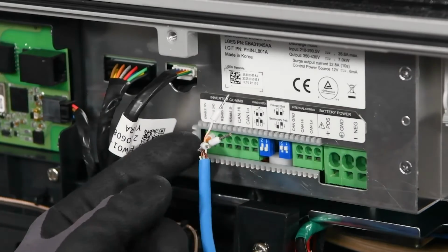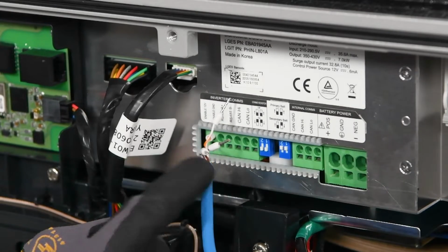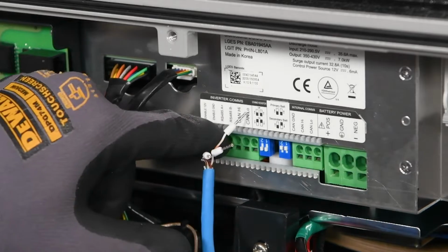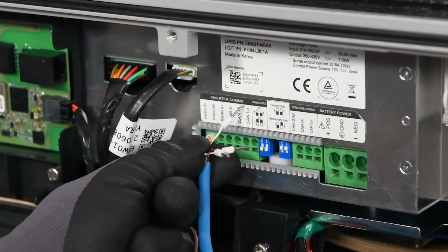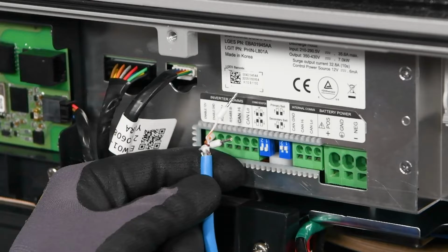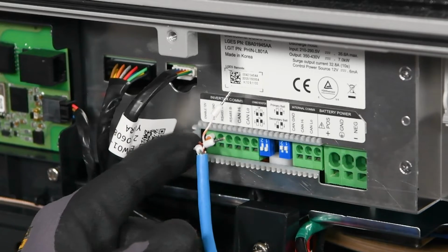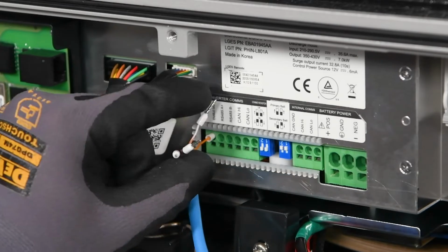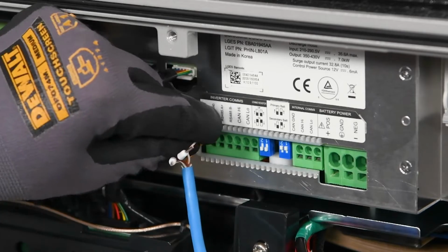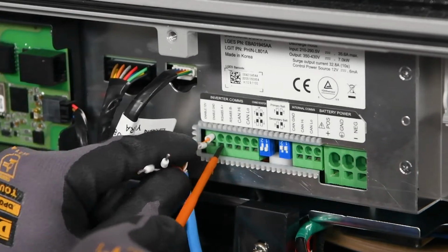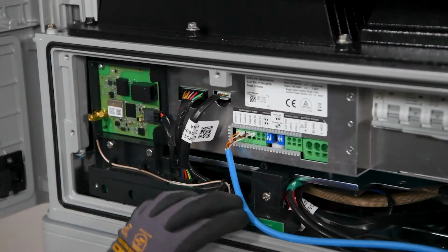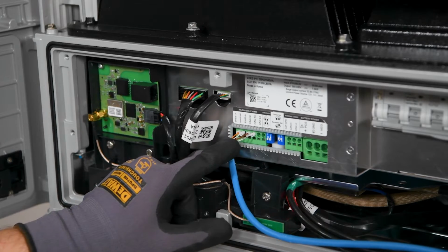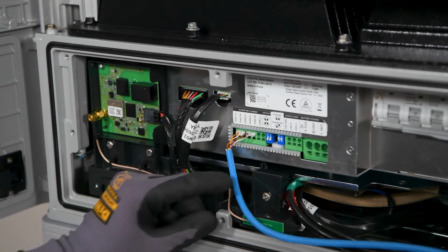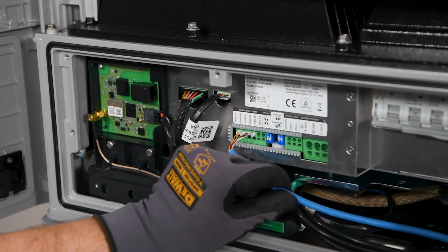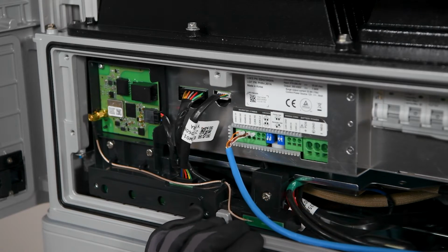So now it's essential as you go along and insert these communication cables into each port to give them a slight tug to ensure that the jaws at the back are actually biting into the cable or the ferruled end. It's going to make sure that you're getting communication across the wires. So now we have our communication cables set up to the inverter comms port. Next, we'll move on to the secondary battery.